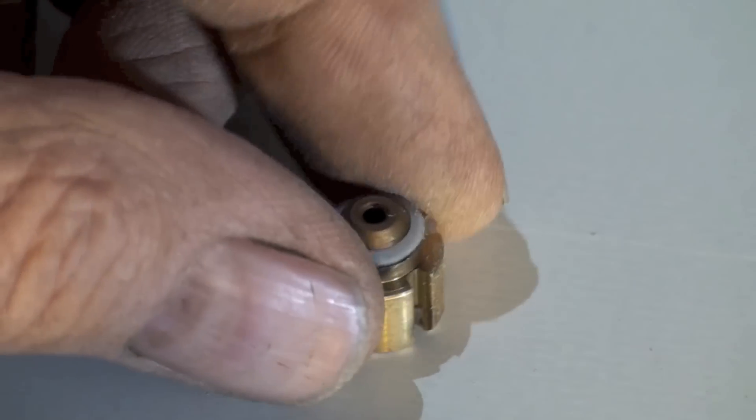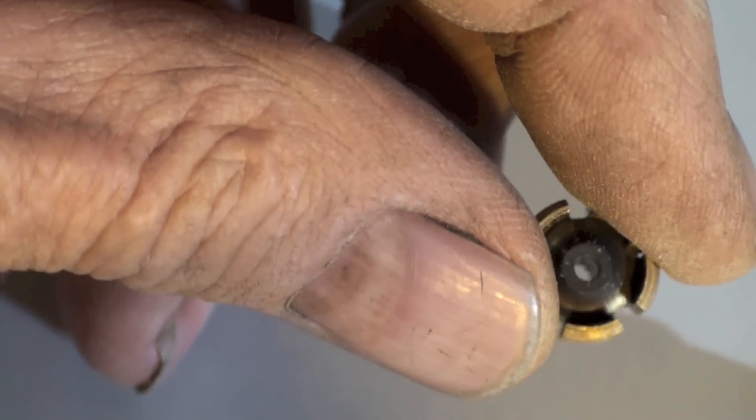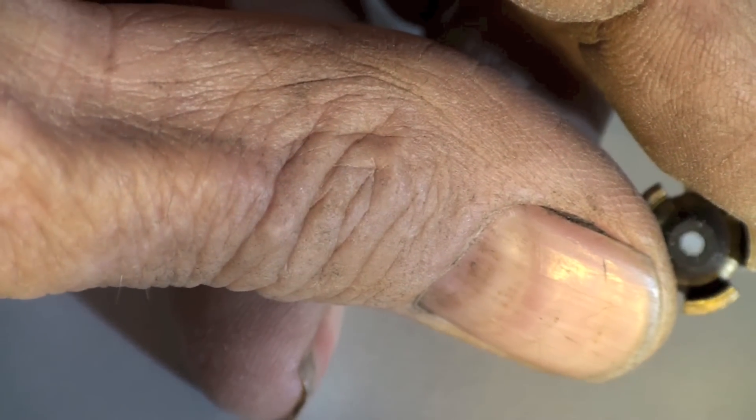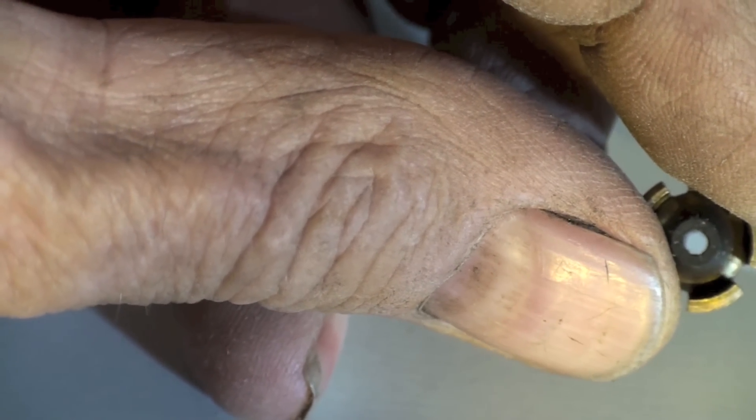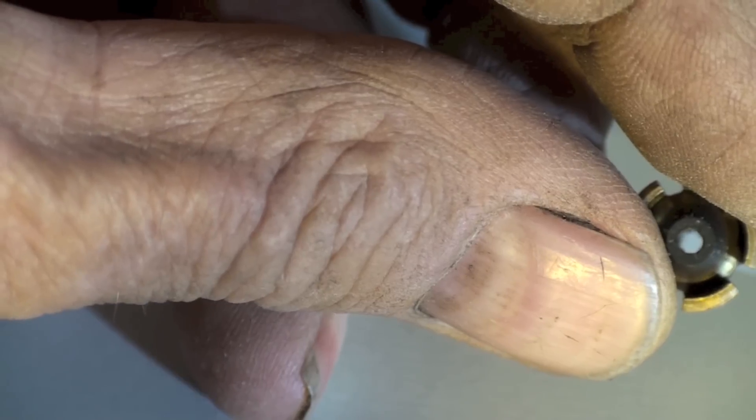Here we have a little closer look at this thing. You can see the hole. This one looks like it's been through compressor burnout. That's the actual orifice right there. That's what the refrigerant is restricted through.